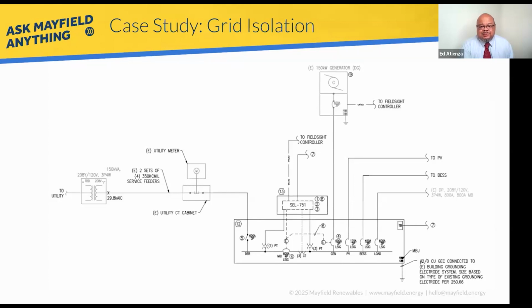What makes this application super complicated is, well, what are we controlling? When we look at the SEL-700G or the 651R and their synchronizing functions, it's really for a single generator. Whereas this application, because of the multiple sources, has the generator rotating machine up top and the BESS over there, requiring that separate controller to route those signals for synchronization, whether to the generator or to the BESS.